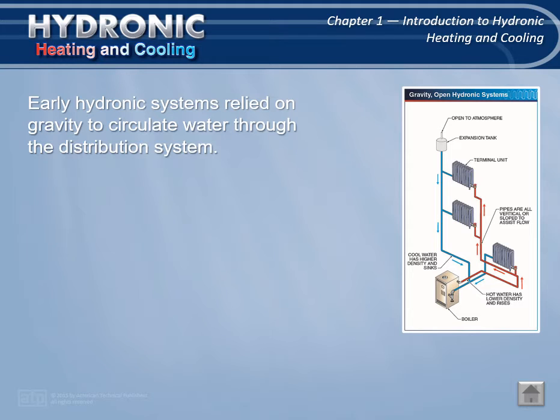An open hydronic system is a hydronic system that is, at some point, open to atmosphere. In these early systems, piping was routed from the boiler to the terminal units using risers and upwardly graded piping. At the top of the system, an open overflow pipe was connected to an expansion tank that provided for thermal expansion. A return pipe conveyed water back to the boiler. As temperature and limiting controls were developed, these systems became more popular.